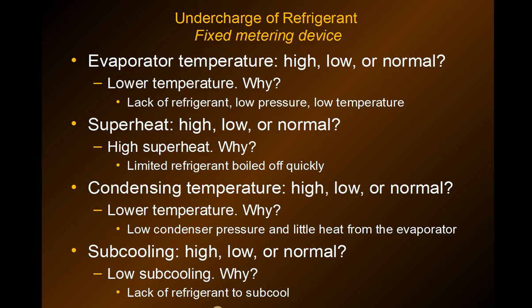For an undercharged fixed metering device system, the evaporator temperature will be lower than normal because too little refrigerant causes low pressure and low temperature. The superheat is going to be higher than normal because there's not enough refrigerant to boil off throughout the entire evaporator — it boils off quickly early on, and then picks up more superheat than normal.